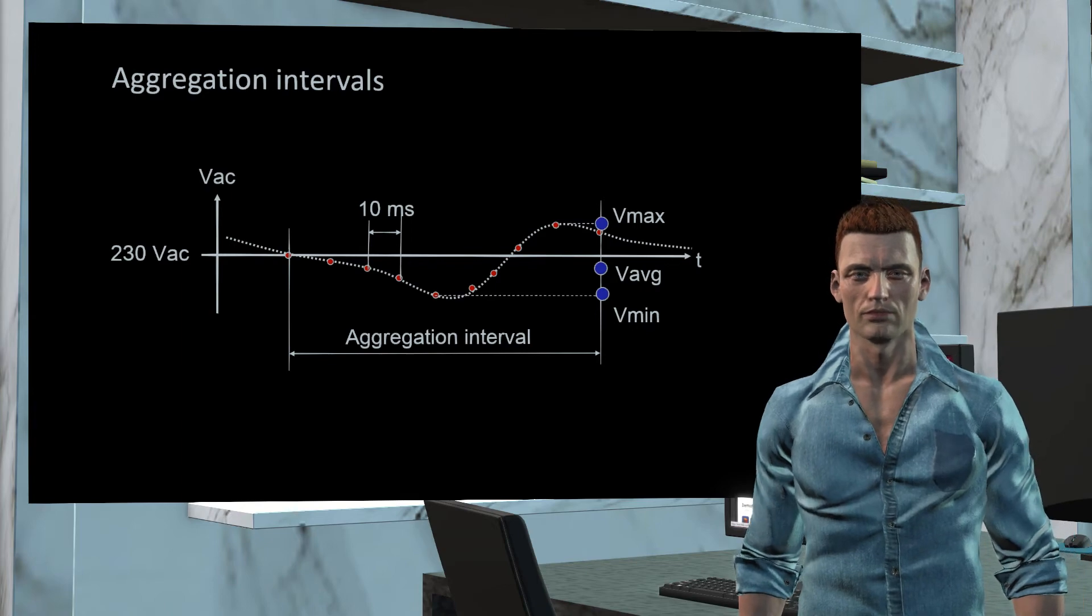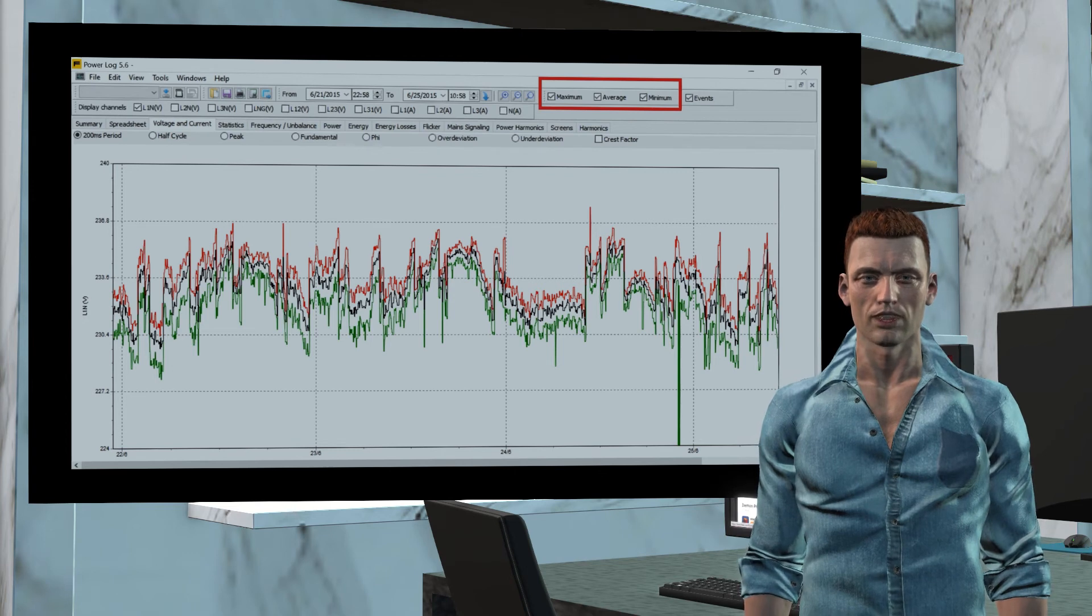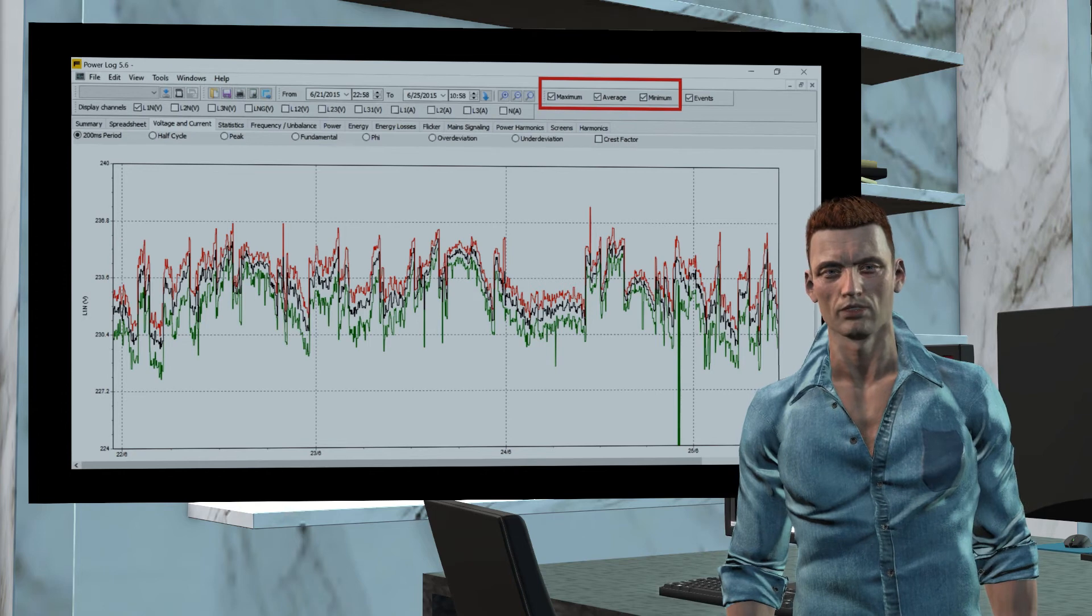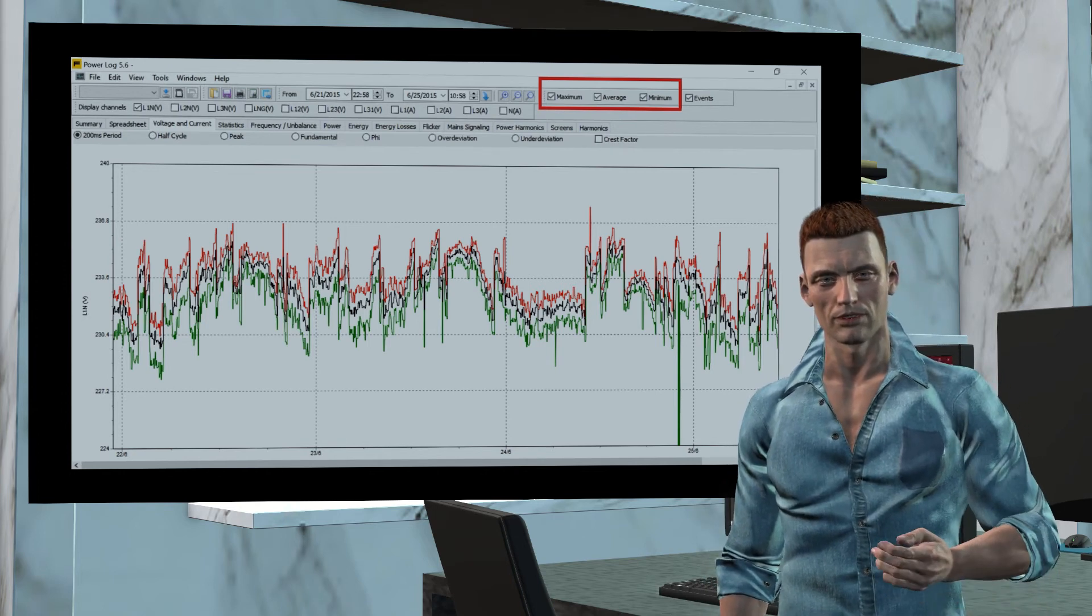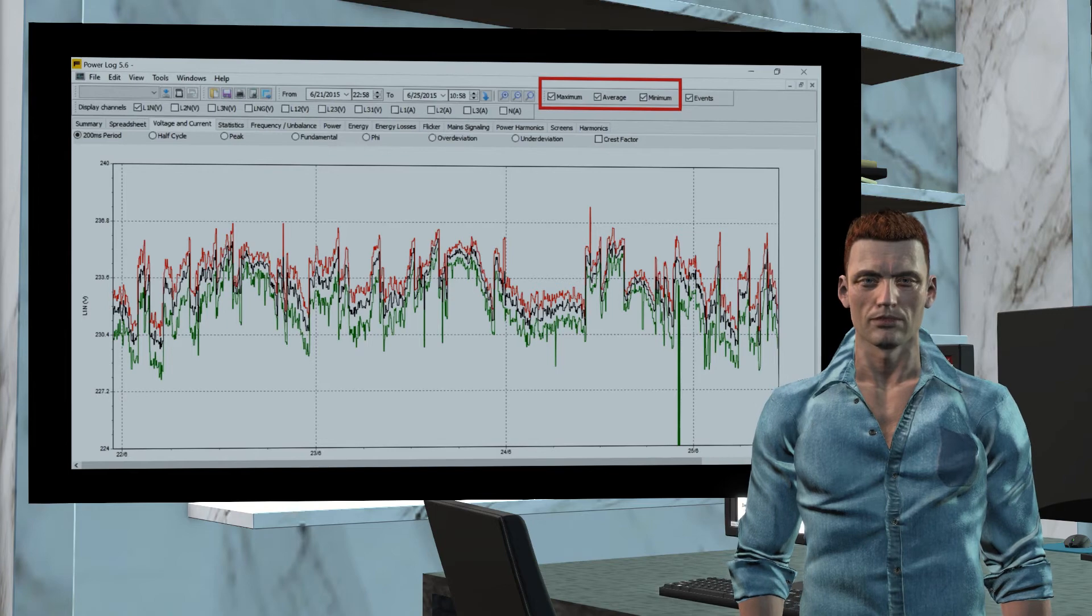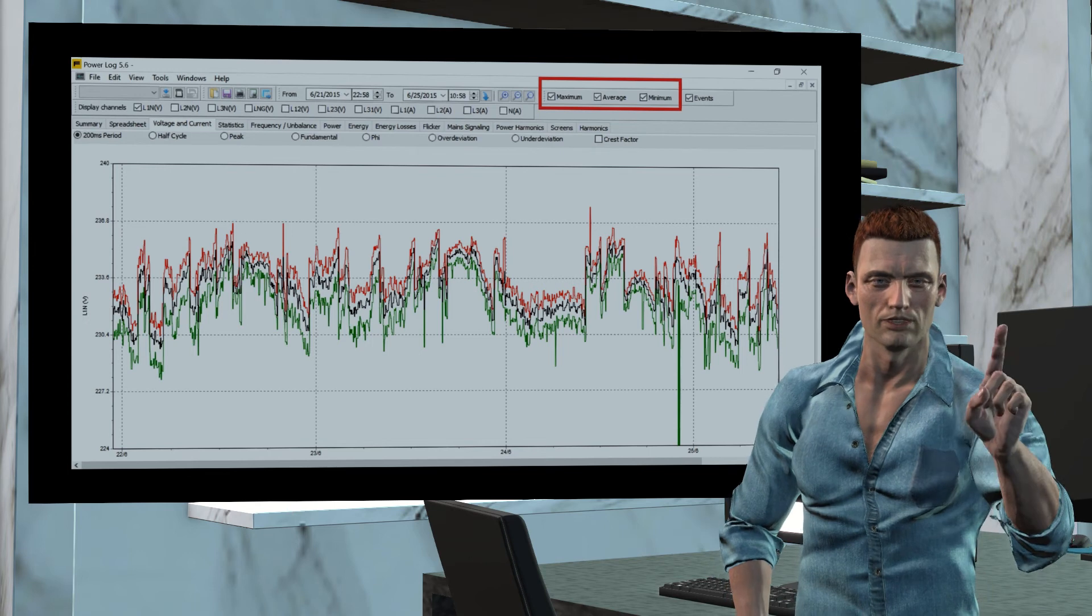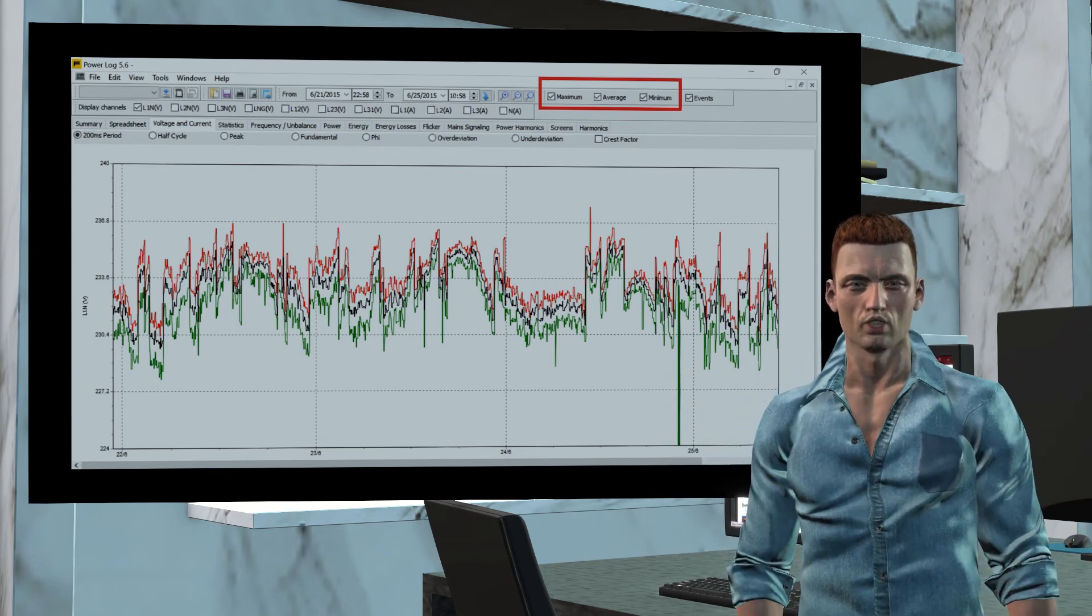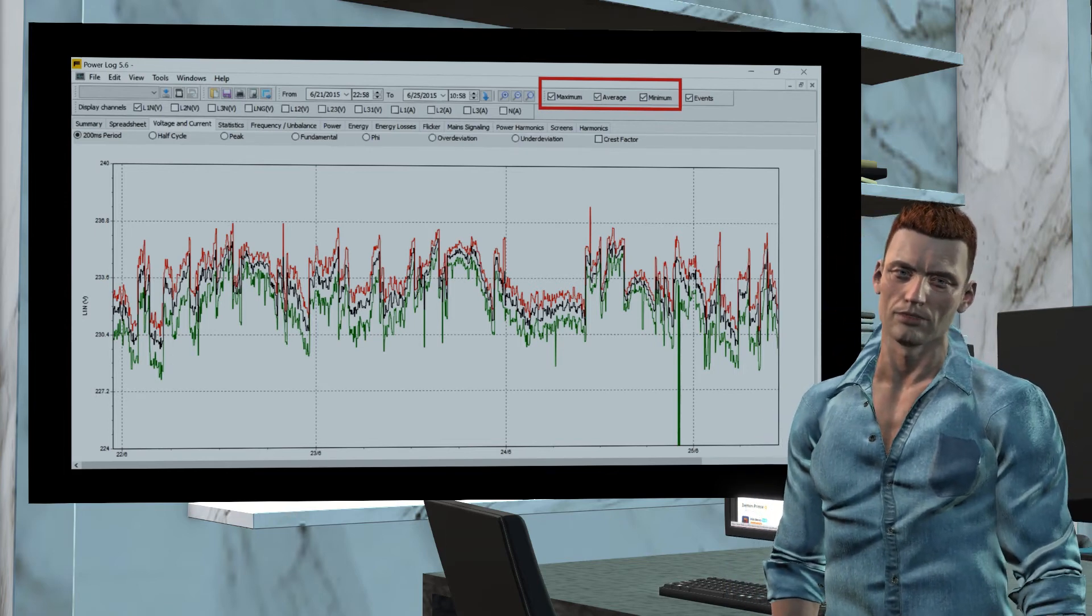For this reason, if we open a data file with PowerLog software supplied with the Fluke 430 power quality analyzer, and for simplicity we select to display only the voltage trend for phase 1, then we will see 3 graphs in red, green and black colors. These graphs correspond to the graphs that are obtained with the maximum, minimum and average values respectively, obtained for each elapsed aggregation interval. Quite logically, the red graph of maximum values is in the upper side, the green graph of minimum values is in the lower end, and the black graph of average values is between the trends of maximum and minimum values.